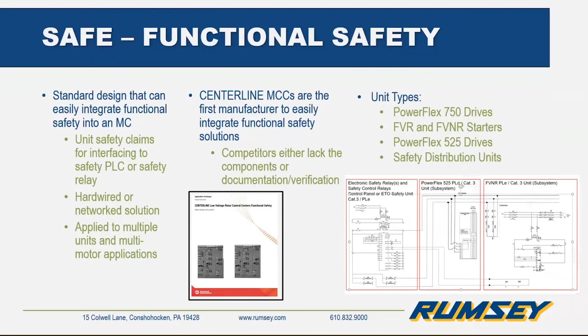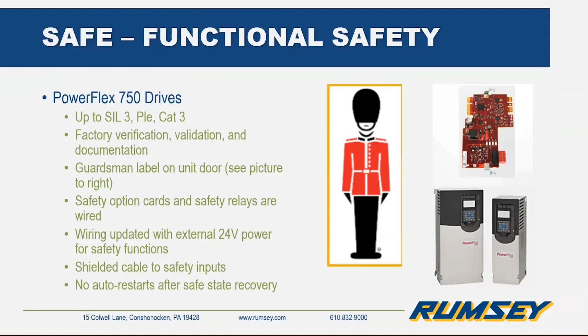So hopefully some of you recognize the Guardsman logo that you see here, as it's found on Rockwell's safety products, such as the Guardmaster switches. You may now also be seeing this on certain PowerFlex 750 MCC units, and that also comes with a SIL 3 PLe Cat 3 rating. This gets achieved basically by adding shielded cable, external 24-volt power for safety functions, and safety relays and option cards. This safety rating is verified, validated, and documented at the factory before it even ships. And like I mentioned, the little logo will actually be on the unit door.